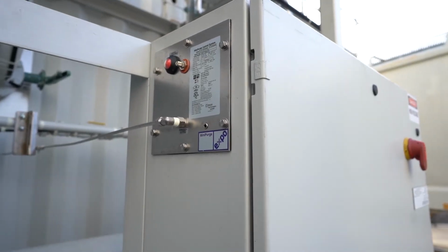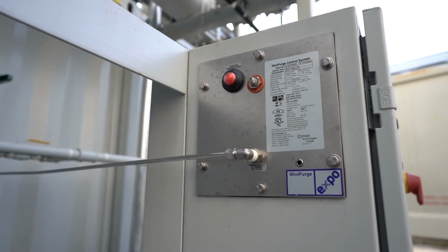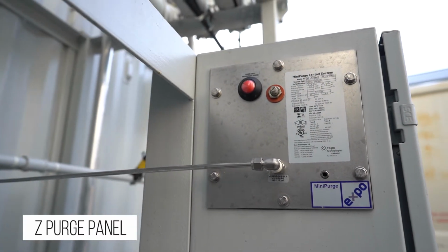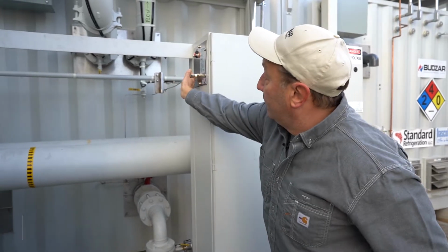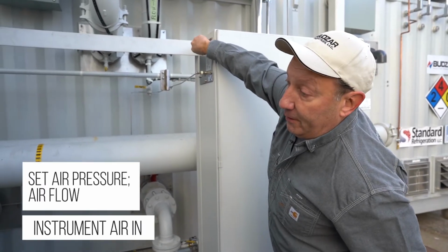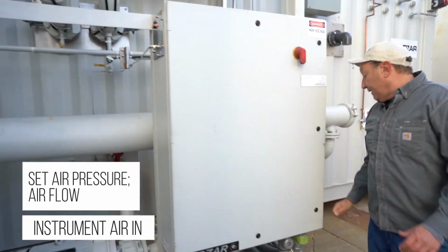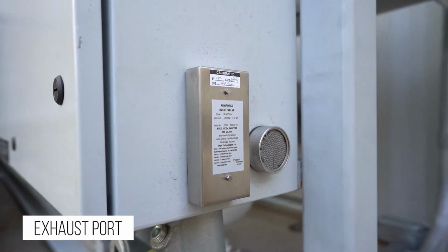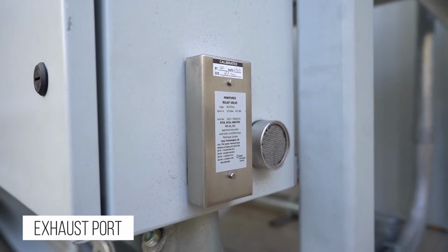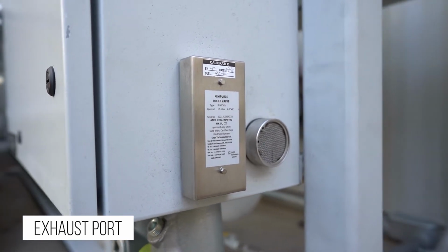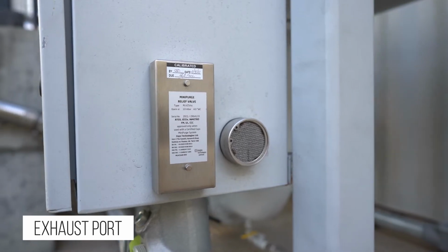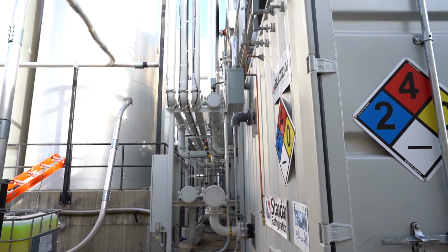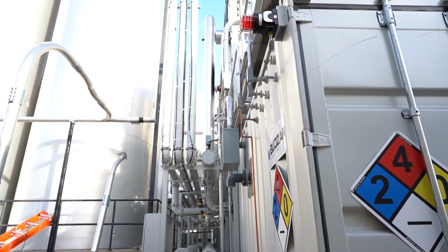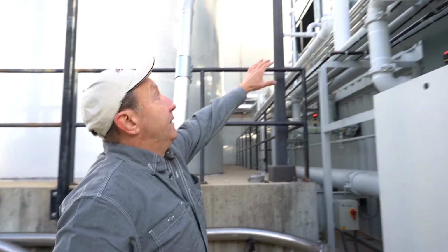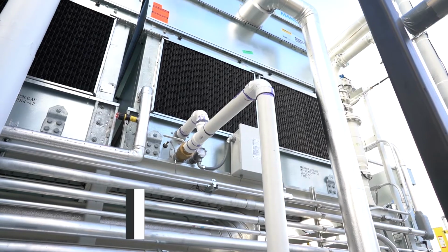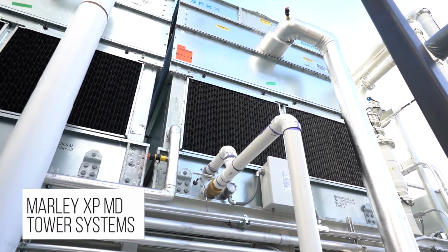Okay, just like the enclosures inside the container, this enclosure is also protected by the Z-Purge panel made by Expo. This is where the instrument air comes in. This is where we set the air pressure, air flow. And then on this side, we have an exhaust port that has a specifically sized orifice plate to allow a certain amount of airflow through the cabinet. And then we have a relief valve. The purpose of this is to keep any arcing or flashing, any sparks away from the propane in the event of a possible leak. Up above here, we have 3 independent Marley XP MD model tower systems.